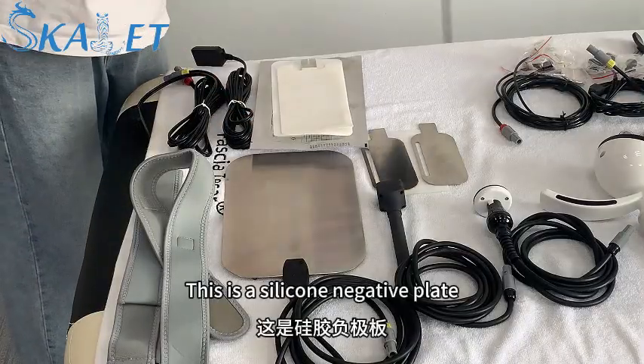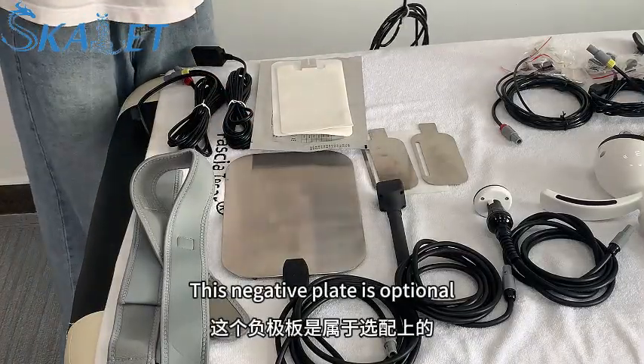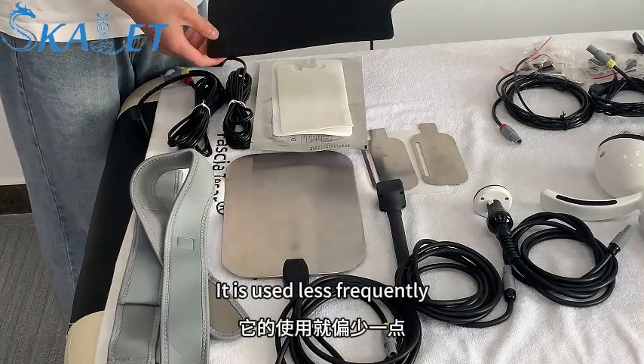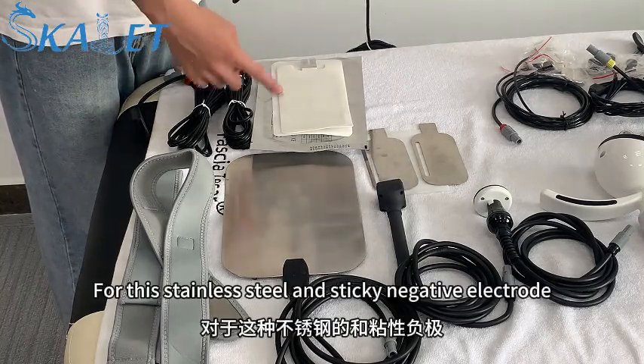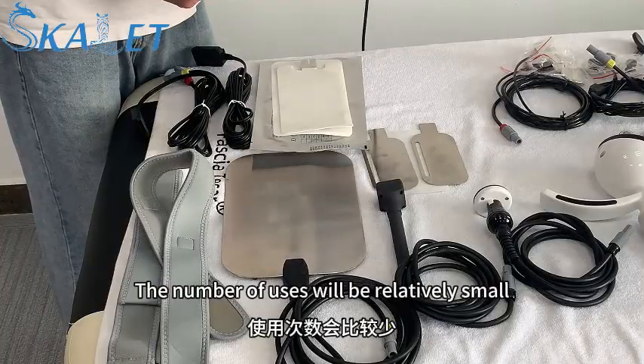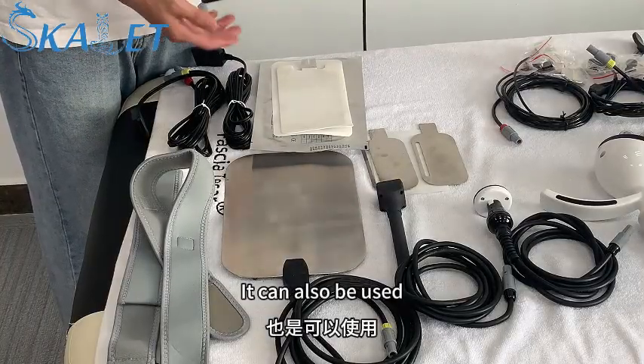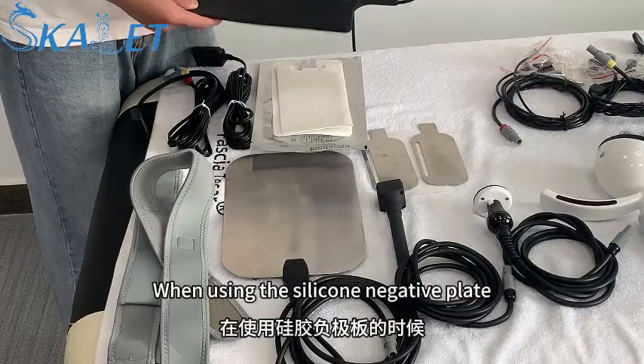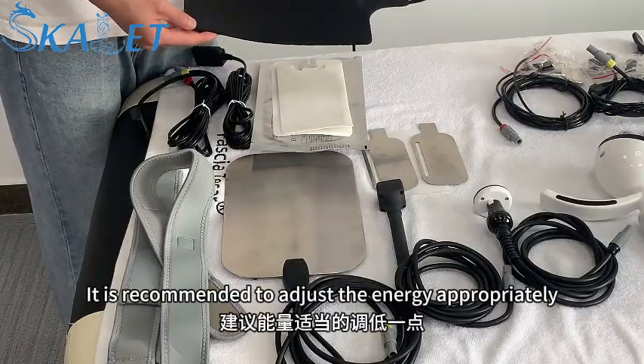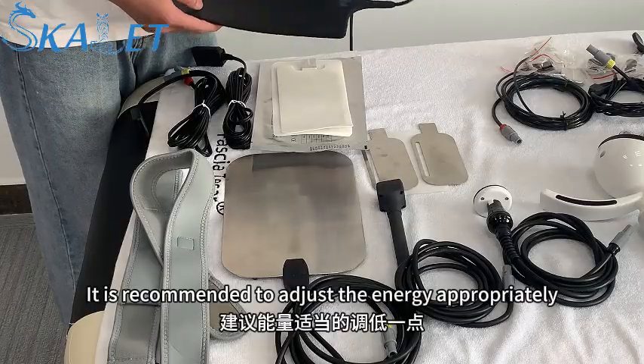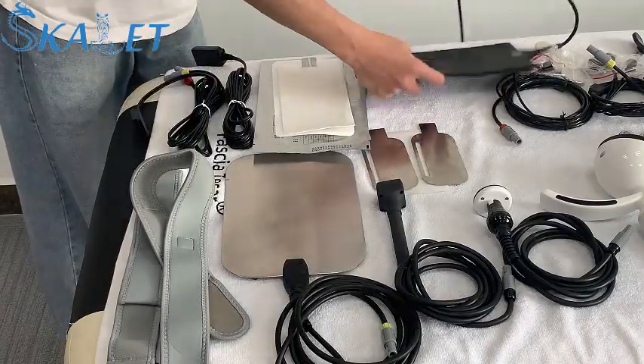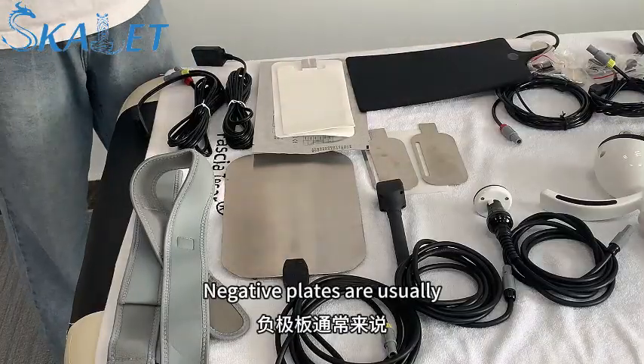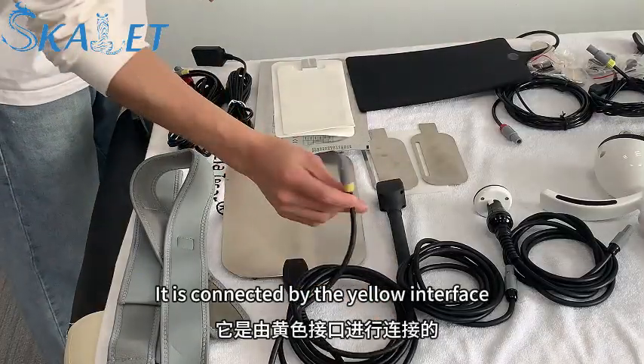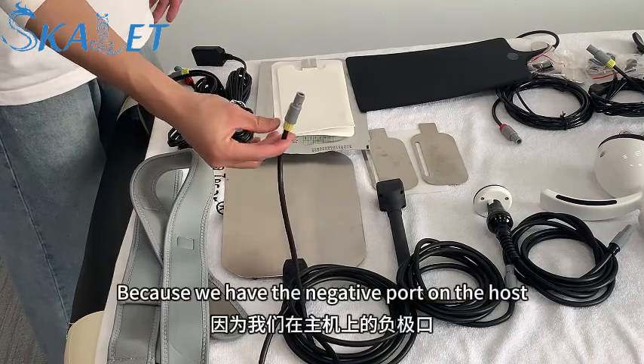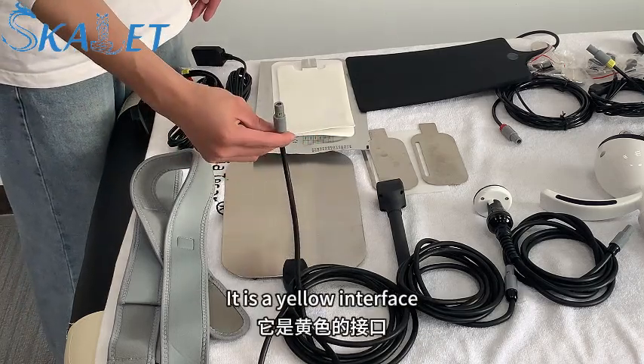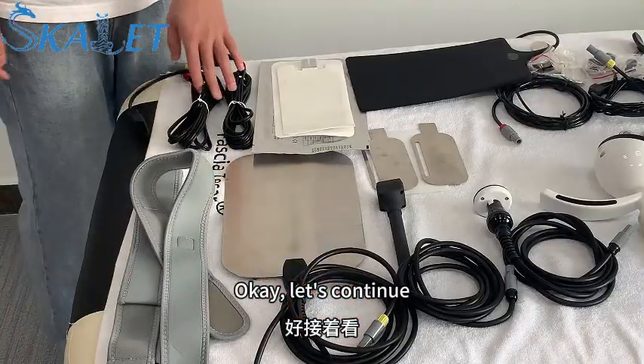This is a silicone negative plate. This negative plate is optional. It is used less frequently. Compared with the stainless steel and sticky negative electrodes, the number of uses will be relatively small. But if the customer likes it, it can also be used for flexible operation. When using the silicone negative plate, it is recommended to adjust the energy appropriately. Don't set the energy too high. It is good to remember that negative plates are usually connected by the yellow interface, because the negative port on the host is a yellow interface. Okay, let's continue.